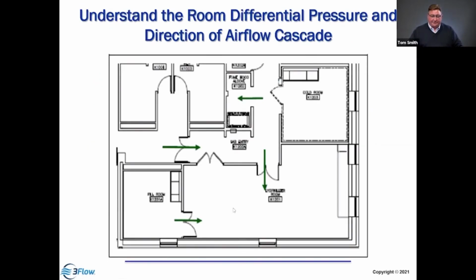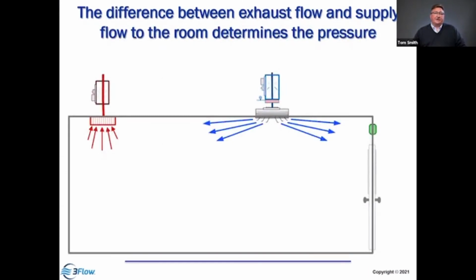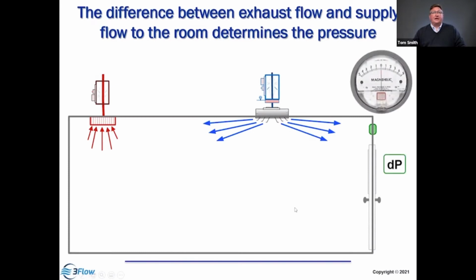If I go back just for a moment to this diagram, the reason that pressurization is important is because if there's a spill or there's an escape from the hood or there's some other type of leak, we don't want that material to be migrating to non-lab spaces. So the air balance is set up to provide a flow cascade from areas of lower hazard to higher hazard, and so that the airflow is in the appropriate direction. And if that is true, we need to know the magnitude of that airflow so that we can determine whether it's improperly balanced.